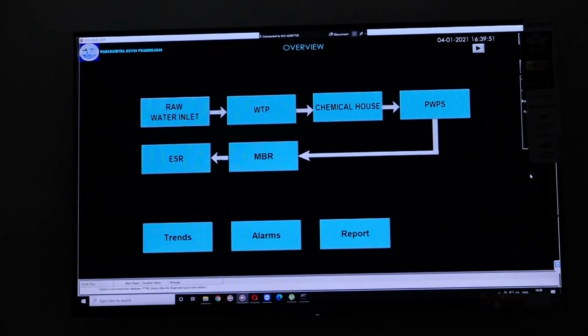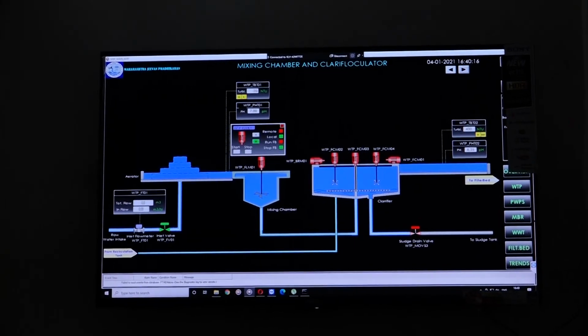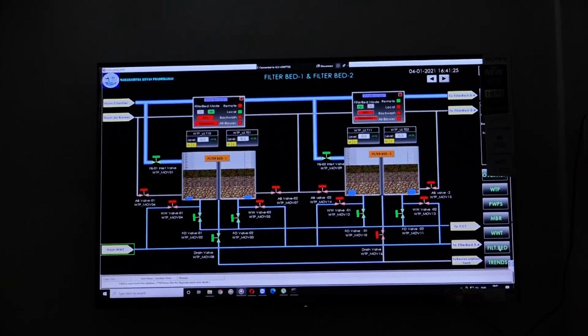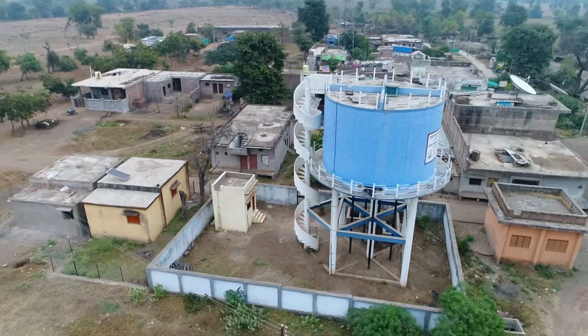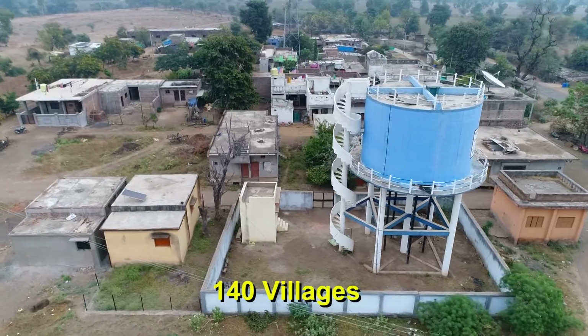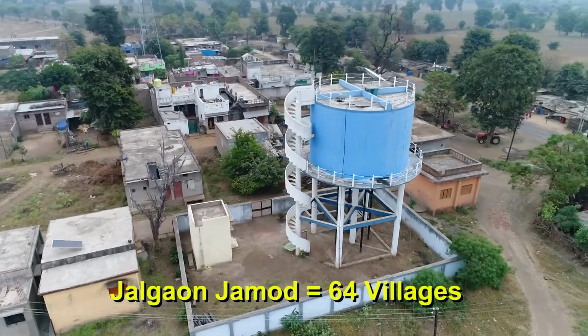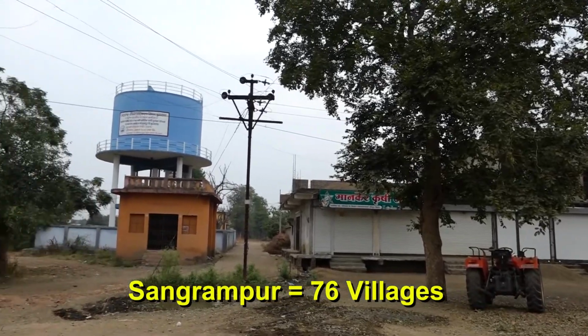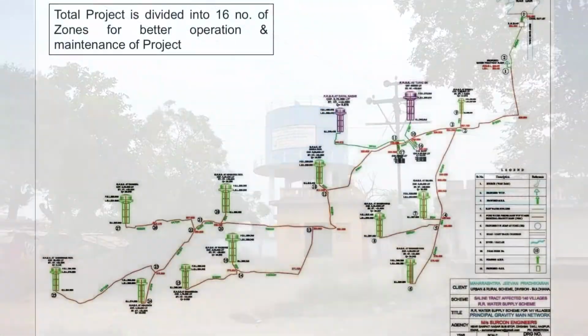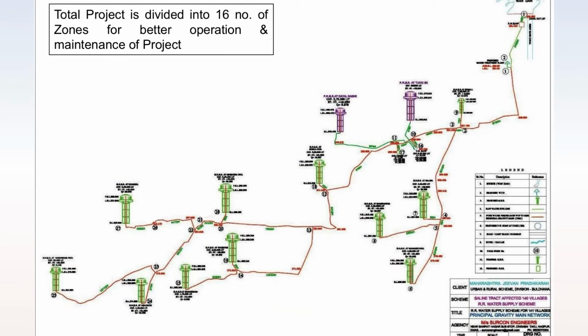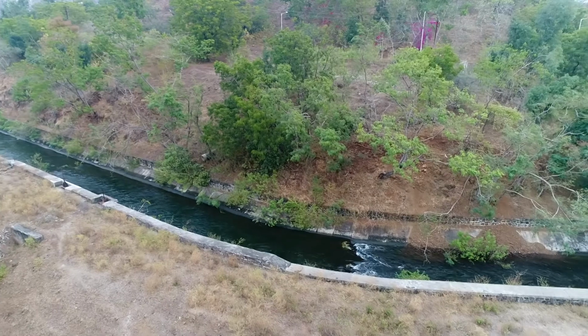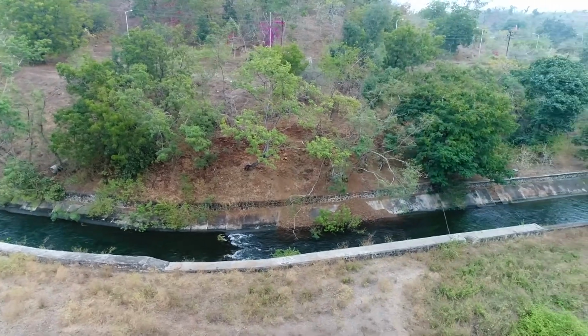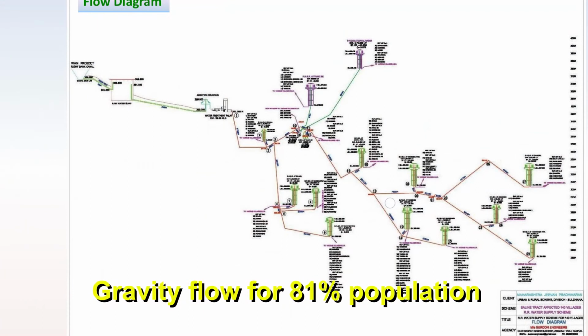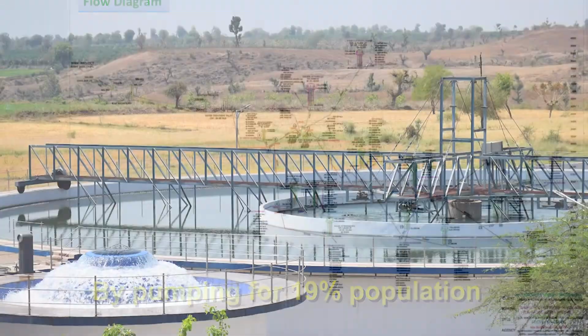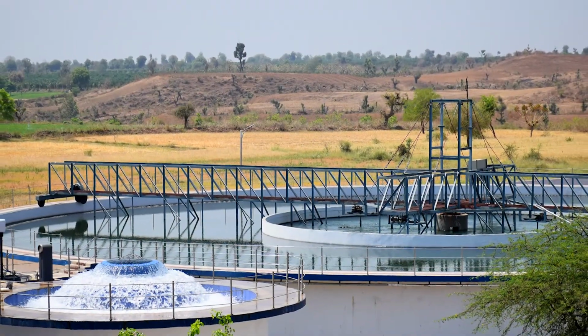Hence, for the first time in Maharashtra, PLC and SCADA system-based operations were introduced in the Regional Rural Water Supply Scheme. This scheme covered a total of 140 villages, 64 villages from Jalgaon Jamod Taluka and 76 villages from Sangrampur Taluka. The total project was divided into 16 zones for better operation and maintenance. The project was designed in such a way that the water was distributed by the flow of gravity for 81% of the population and by pumping for the remaining 19% of the population, making it one of the most techno-economical water supply projects.